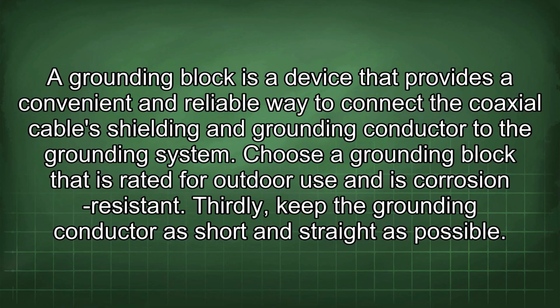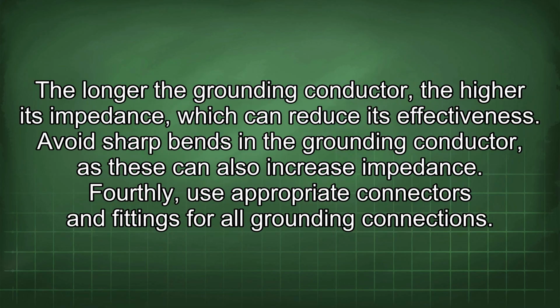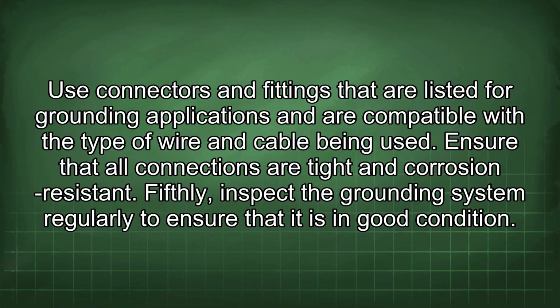Thirdly, keep the grounding conductor as short and straight as possible. The longer the grounding conductor, the higher its impedance, which can reduce its effectiveness. Avoid sharp bends in the grounding conductor, as these can also increase impedance. Fourthly, use appropriate connectors and fittings for all grounding connections. Use connectors and fittings that are listed for grounding applications and are compatible with the type of wire and cable being used. Ensure that all connections are tight and corrosion resistant.